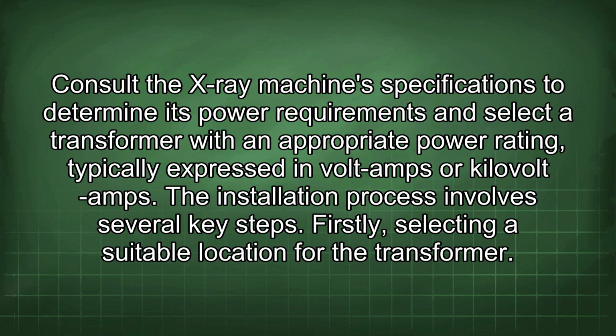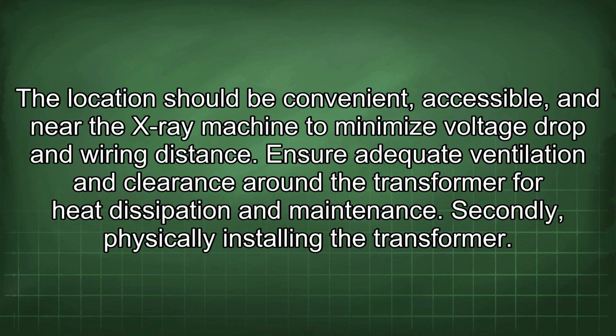The installation process involves several key steps. Firstly, selecting a suitable location for the transformer. The location should be convenient, accessible, and near the X-ray machine to minimize voltage drop and wiring distance. Ensure adequate ventilation and clearance around the transformer for heat dissipation and maintenance.